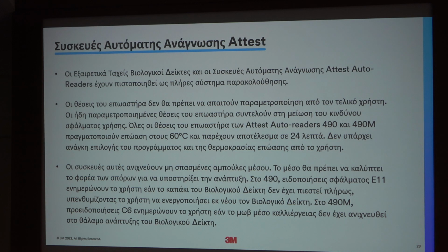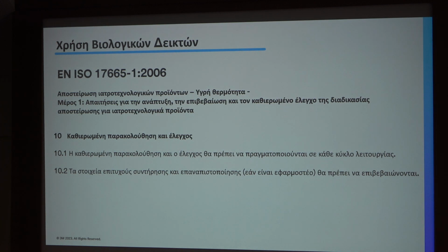And also, the most important thing about the biological indicator is that when it is crushed, the media should meet the spores, because if there is growth, it means the sterilization cycle was not able to kill the microorganisms, and then the spores should grow in that environment. And therefore, if there is a problem with crushing in the wrong direction perhaps, then you should also receive some alarm saying that you have to repeat this again in order to get the right result.